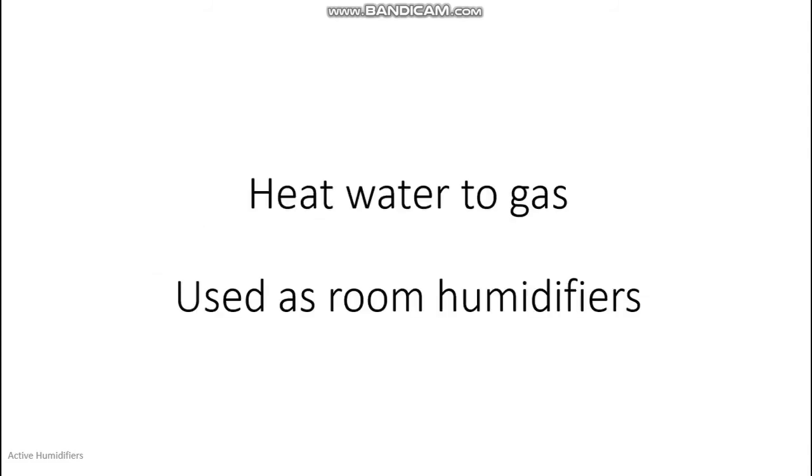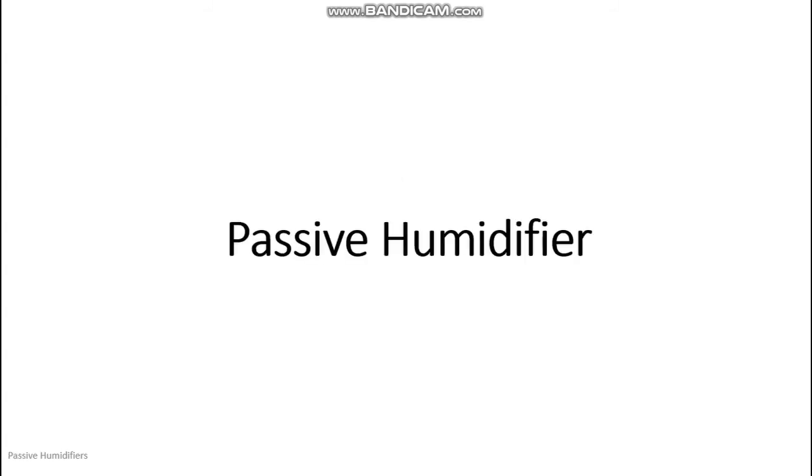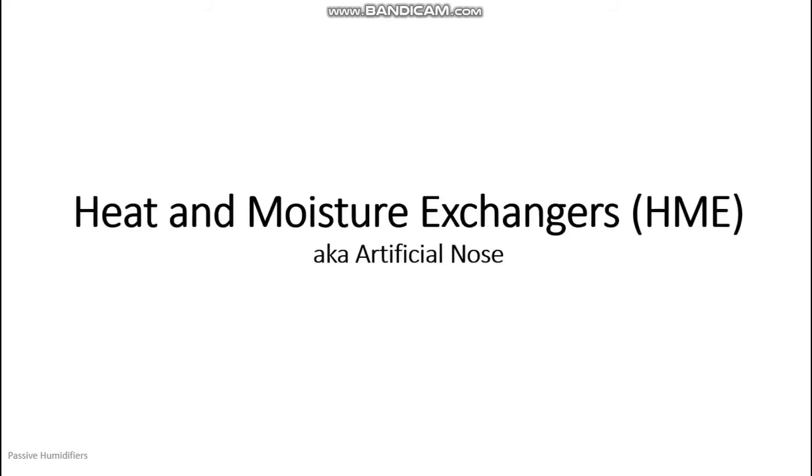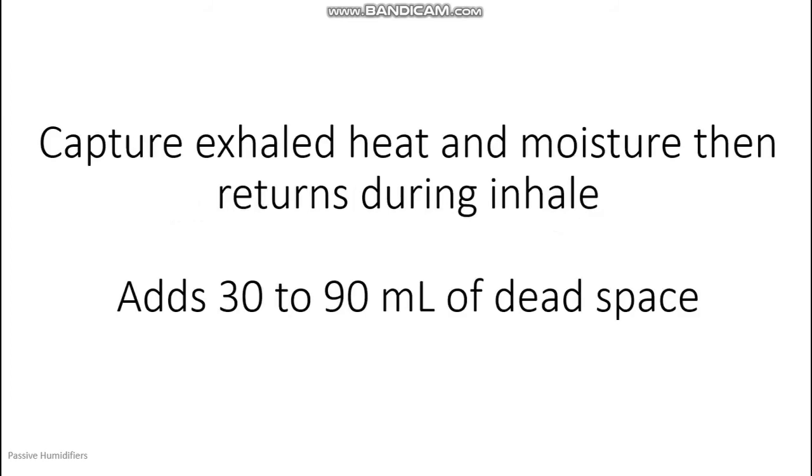Vaporizer humidifiers heat water to gas, and are commonly used as room humidifiers. Passive humidifiers include heat and moisture exchangers, or HME, also known as the artificial nose. This device captures exhaled heat and moisture, then returns during inhale. It adds 30 to 90 milliliters of dead space.